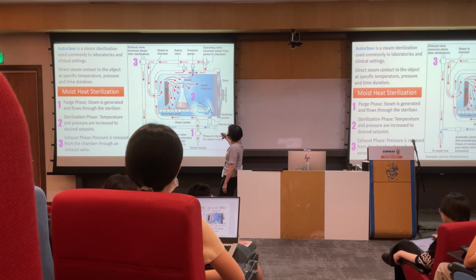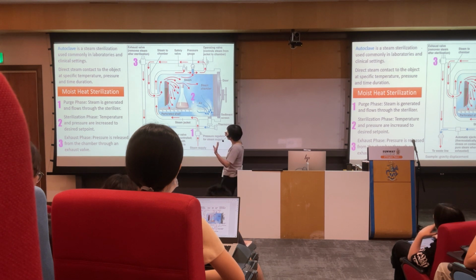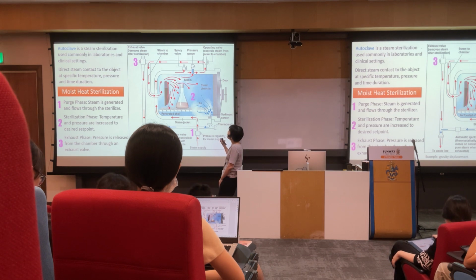It normally takes a pressure of about 15 psi and 121 degrees Celsius for roughly 20 minutes. With these conditions, all the vegetative cells and also the endospores are killed. Once the sterilization is done, 20 minutes gone, then comes your exhaust phase. Exhaust phase means releasing the pressure. Automatically this head will open to release the steam. When it's released, it starts to cool down, and that also takes quite some time. It normally takes about half an hour. Then you can open it and take whatever you want out of the chamber.